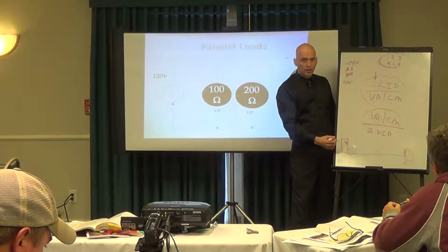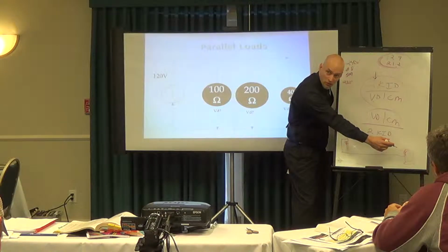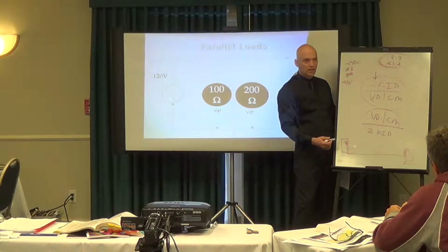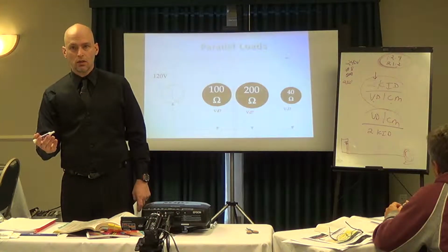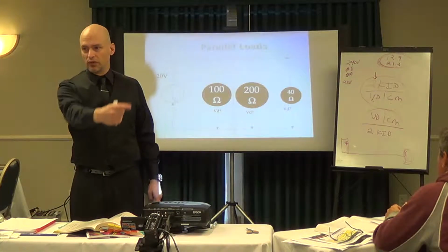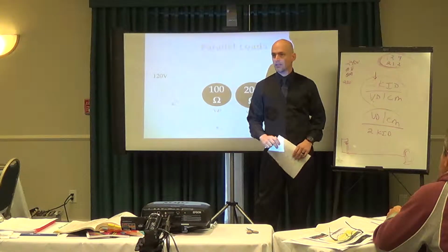Problem with that is, if I've got 200 physical feet, I've got to have a pathway for it to go out there 200 feet, and then turn around and come back to the panel. Or in this case, if I've got 2 phases, I've got 2 paths. One way or the other, I've got 2 lengths of wire. Each length is 200 feet, so the total length of wire is 400 feet, and that's what the 2 does, it doubles that, so it accommodates for the wire. Make sense? And the K being the resistive value of the wire, it doubles the resistive value of the wire, so we've got it all wrapped up in a nice nutshell.